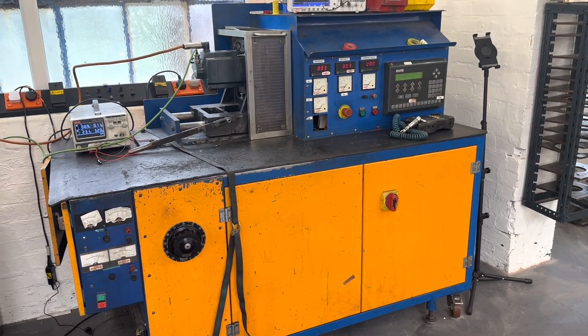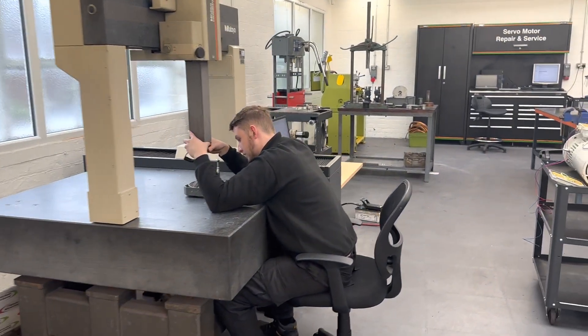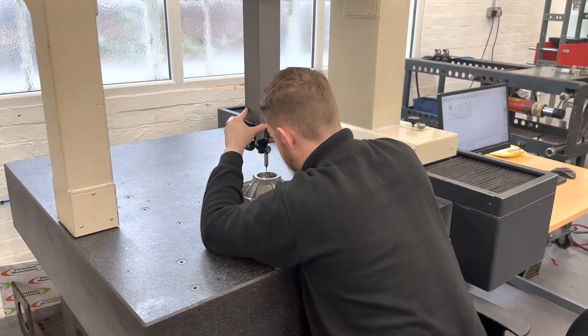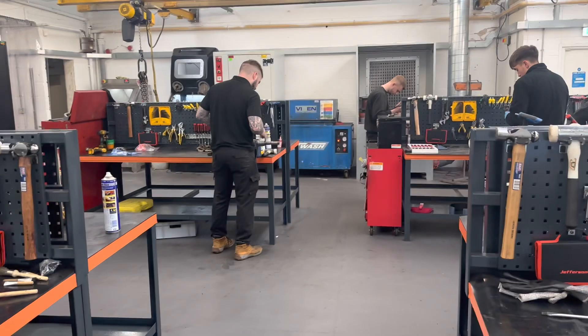This is actually one of the oldest pieces of equipment — I remember having a hand in designing this about 20-25 years ago. Of course servo motors are still mechanical electrical pieces of equipment, so we have to measure everything: bearing journals and housings down to micron levels to make sure everything is correct before it goes back.